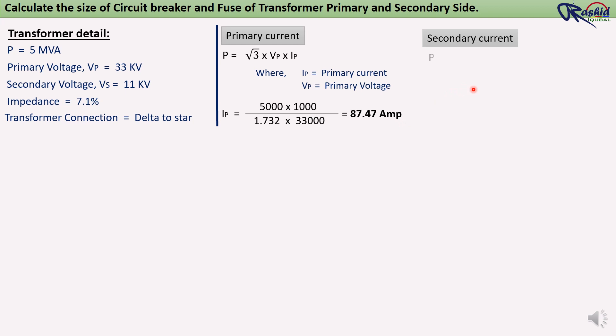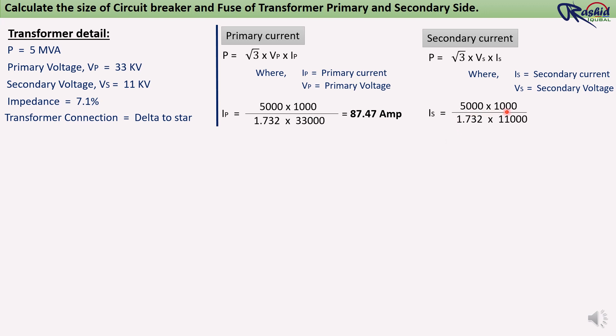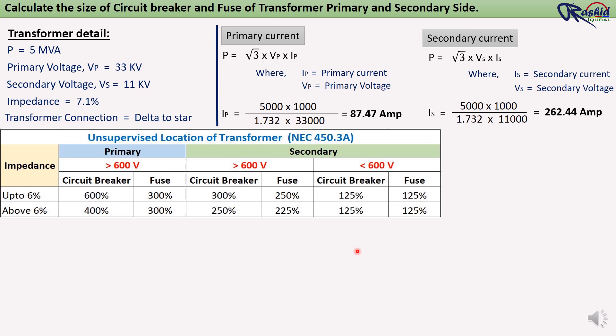For secondary current: P = √3 × Vs × Is. Putting in the values: (5000 × 1000) ÷ (1.732 × 11,000) = 262.44 ampere. This is our secondary current. Referring to the NEC standard, both primary voltage (33 kV) and secondary voltage (11 kV) are more than 600 volts. So we will follow this option: multiply 250% for circuit breaker calculation and 225% for fuse calculation at the secondary side.